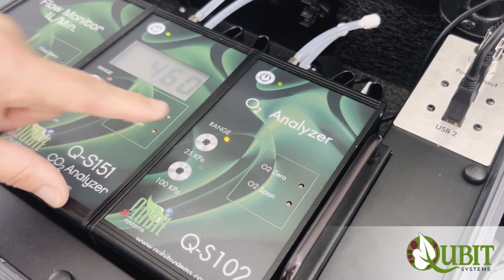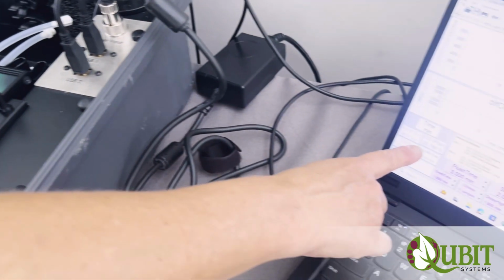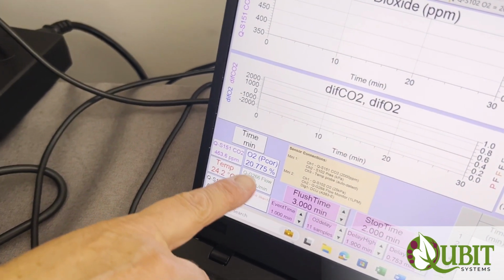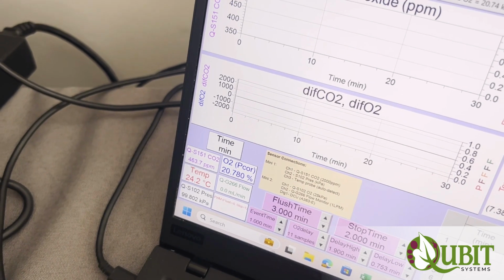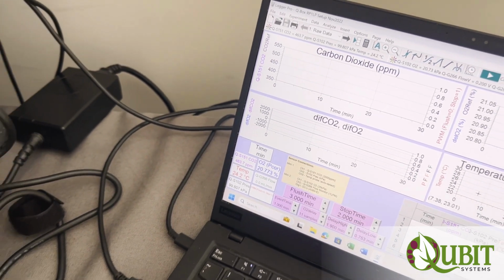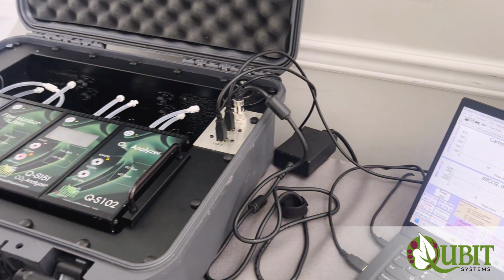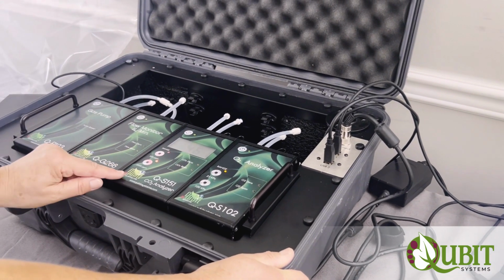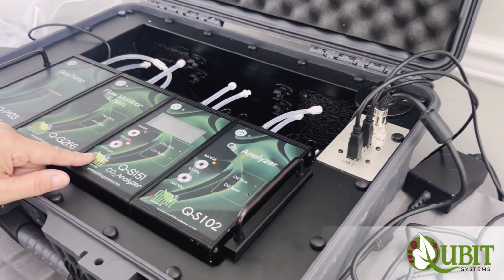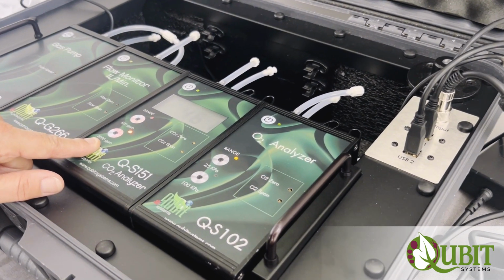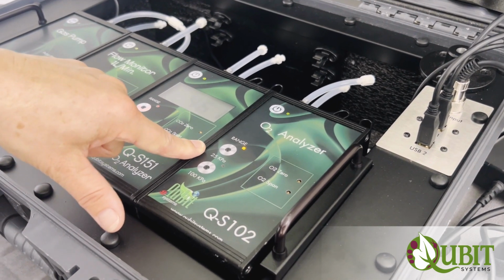When you change that, you will see that the reading in the software is now correct, or close to being correct, 20-point-something% oxygen rather than 5, which is what the reading was before. So it's very important that the ranges are selected correctly, 2,000 parts per million for CO2, 25 kilopascal for oxygen.